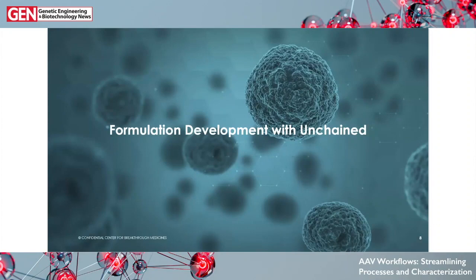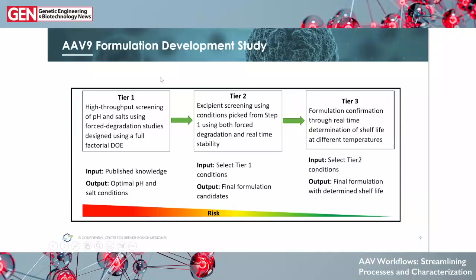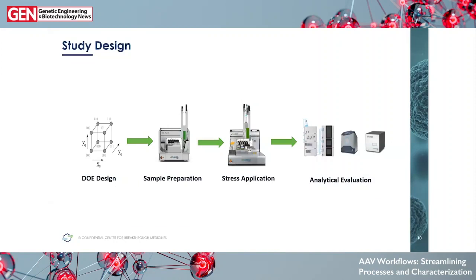Thank you, Tatiana. I'm excited to talk about some of the formulation development activities we do here at CBM using our Unchained Labs equipment. For an example, I'll talk about AAV9 formulation development, using a tiered approach. Tier one uses high-throughput screening with pH and salts using forced degradation studies, with a full factorial DOE because we're focused on just pH and salts as a base case. From there, we move to tier two for excipient screening, building upon what we learn in tier one. Finally, tier three takes all leads to determine real-time stability and shelf life.